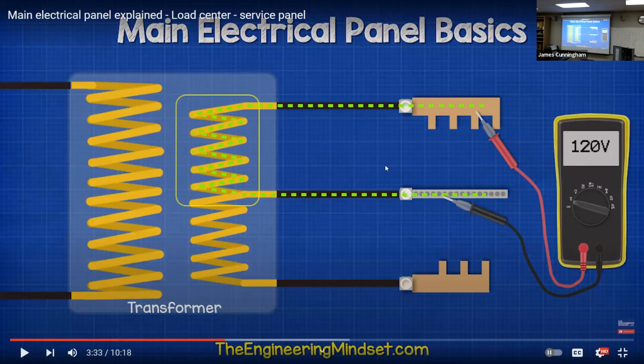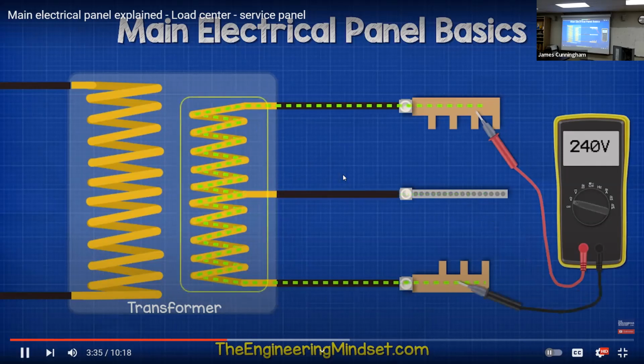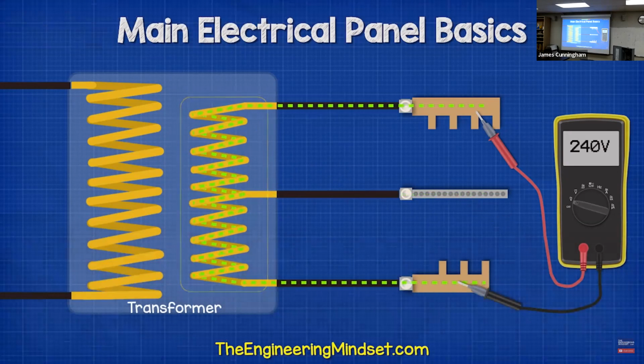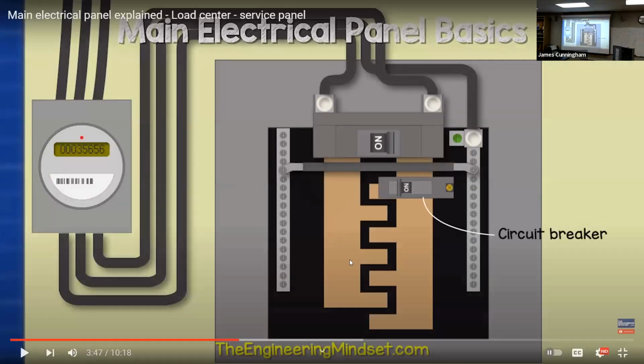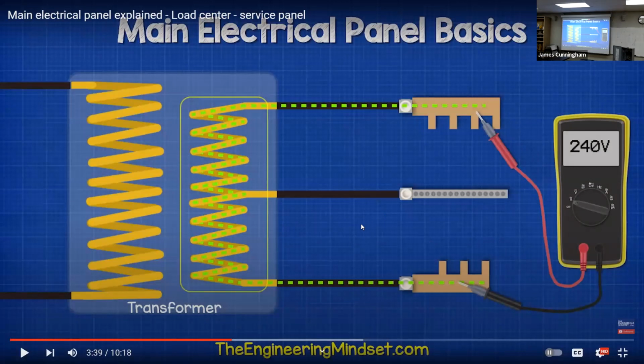I find this really interesting, the way they do this. They're only using half of the windings on the coil for each leg. Maybe it's me, but I think this is really interesting. When we connect to the 2 bus bars, we're connecting to the full length of the coil, so we're picking up the full voltage which the transformer can provide. Therefore, we get 240 volts. Now, I just want to go back a little bit. Remember, it's an AC current, so the current is going in both directions. That's what he's showing back and forth.